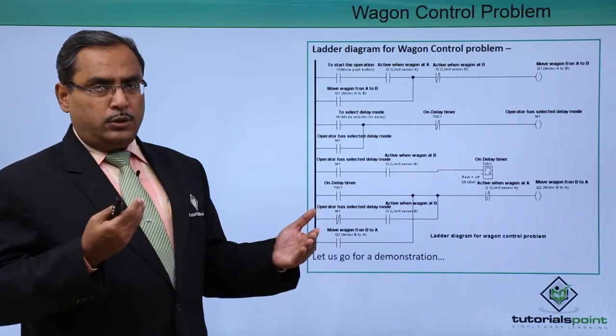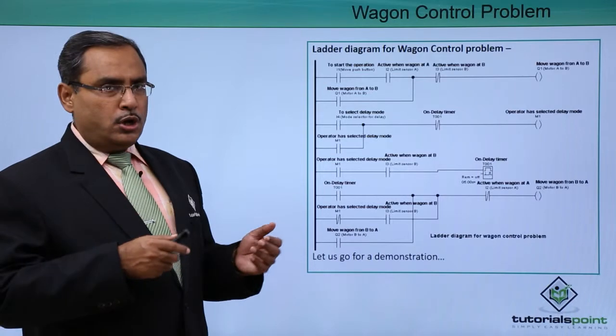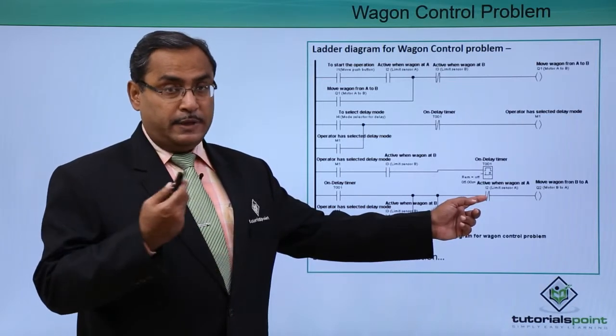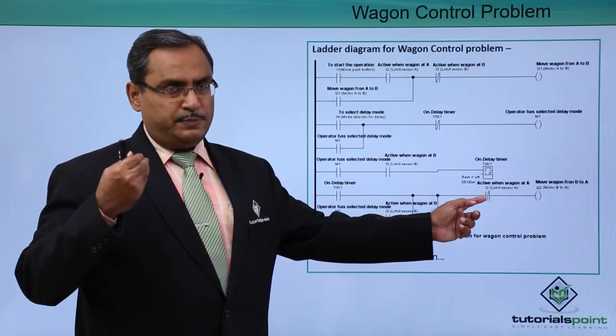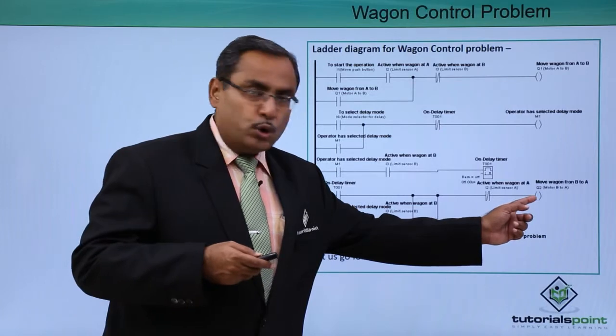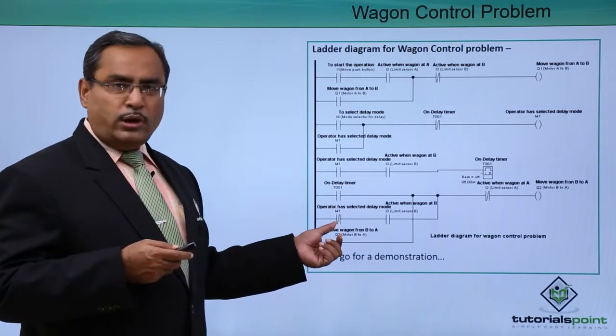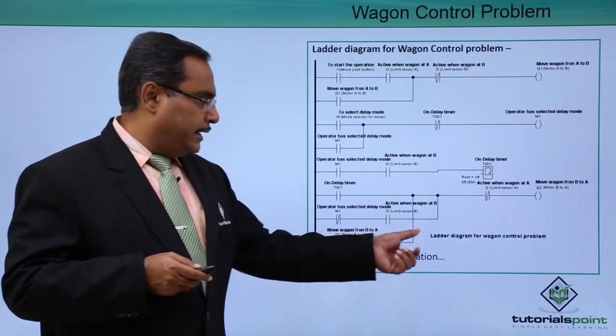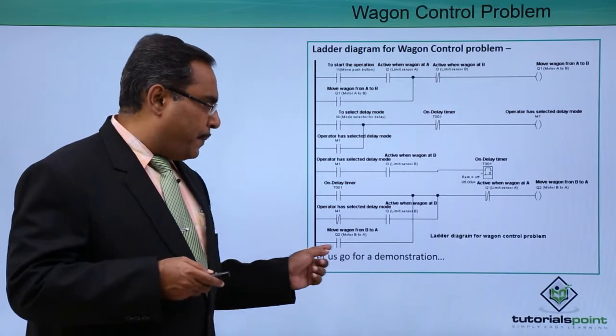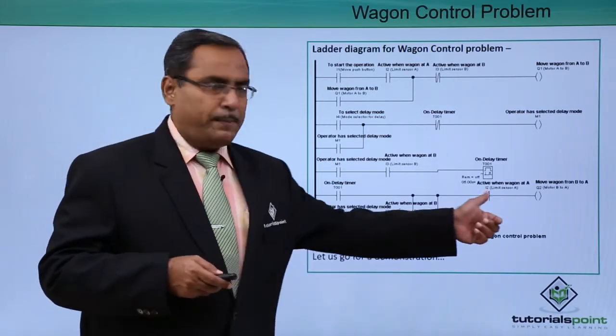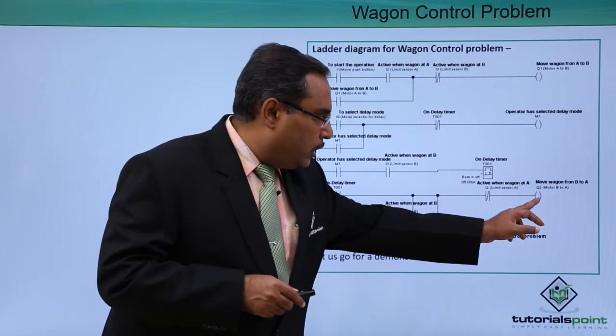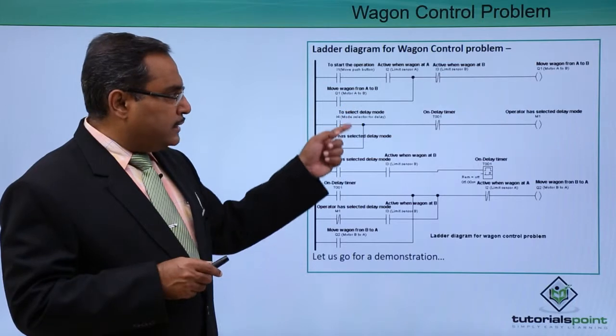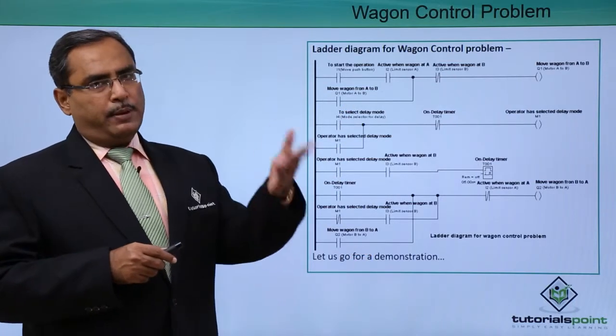When the wagon returns from B to A, there are two modes. Mode 1: when the on-delay timer is on, after 5 seconds the move from B to A is initiated until limit sensor A is reached. Mode 2: when the delay mode has not been selected and the wagon is at limit switch B, the return journey is immediately initiated via a parallel path. The motor moving the wagon from B to A will remain on until limit A is sensed. The simulation testing of these outputs will be done in the practical demonstration.